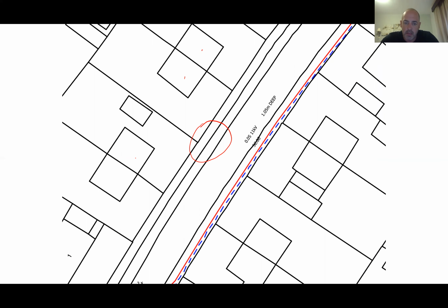The other thing as well is that if you look here, you'll see 5C, okay, which means 5 core. That LV cable is a 5-core cable. And typically, when you have a 5th core in the cable, the street lighting is fed off it. Okay, so again, sometimes this information isn't always carried over when we overlay. Is it that important? I don't know. They're just observations, these, everyone. So just things that I look at. So we've got 5C here, LV here, pole over here.